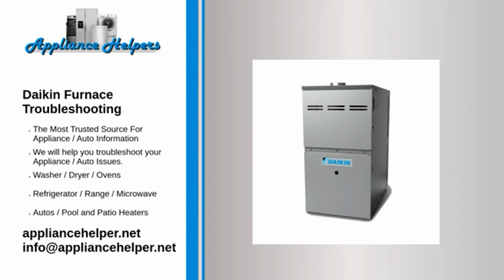Starting and then stopping shortly after. Your furnace's flame sensor checks if a flame is present. If it's defective or there's debris, it won't be able to detect a flame. If dirty, carefully clean the sensor using a fine abrasive pad. If still not working, replace the flame sensor.